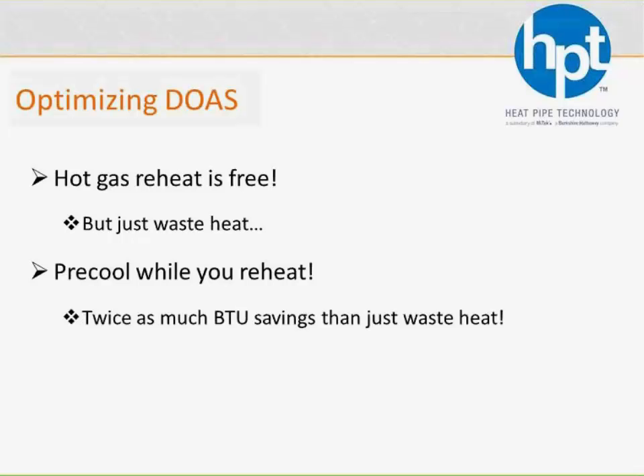It's really the only device that's going to save you on both the upstream side and the downstream side of the cooling coil. So you're going to get twice as much BTU savings with a wraparound heat pipe as you would with hot gas reheat. And not just that, that pre-cooling has allowed you to reduce the capacity of your cooling coil. And what I want to show you here is that you're not just able to reduce the capacity of your DOAS equipment, but you can make that net equipment, let's say, that packaged equipment, more efficient from an EER standpoint.